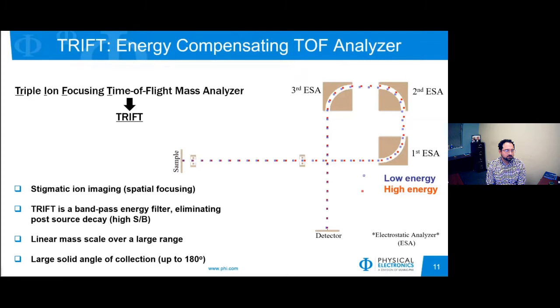Now that we've talked about how the ions are generated, how they're extracted, and the different types of mass analyzers, what kind of advantages does TOF-SIMS have? What kind of information can you gain from it? The advantages of TOF-SIMS are detection of all elements and isotopes: hydrogen, helium, oxygen 16 and 18, etc. You can get molecular information, both organic and inorganic. You get parallel detection with a time of flight mass spectrometer, so you get the full mass range. You're not just picking and choosing a few select species to look at.